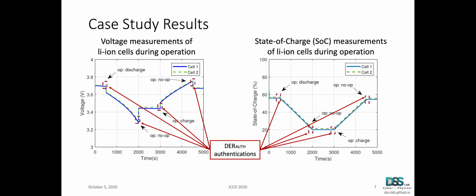To assess the operation of DERAUTH within the test setup presented in the previous slide, a modified version of OpenDNP3 integrating DERAUTH is deployed in two different computers connected via an Ethernet switch. The DNP3 communication protocol runs over TCP/IP, and the master and outstation are configured to interchange 64-bit float analog values. In this case study, the master device initiates the DERAUTH authentication process every time it sends a new setpoint command to the outstation controlling the DER.